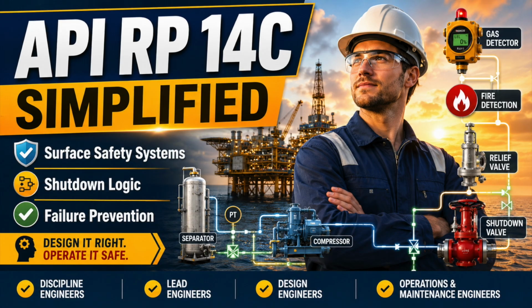This is why cause and effect logic matters. But the logic diagram alone is not enough. A high-pressure signal may be correctly programmed, but what does it physically shut? Does it close only the vessel inlet? Does it shut the producing well? Does it stop the upstream pump? Does it isolate the compressor? Does the closure create block discharge upstream? Does the process pressure rise faster than the shutdown valve can close? Does the relief system receive a new load? A signal is not safety. The final physical state is safety.